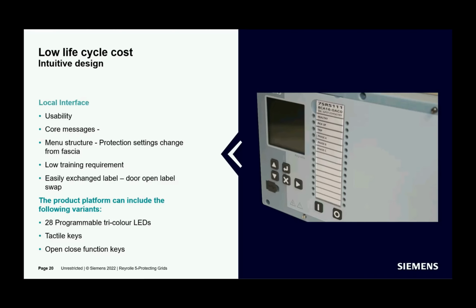What is more, the user can change all the settings of the protection configurations inside the fascia. For example, after entering the predefined settings password, the menu allows you to change any threshold value of any protection configuration, or enable or disable the protection functions altogether. So you don't need the configuration software once the relay is initiated and started. The menu is simple and button interaction with the menu is intuitive. Therefore, this provides low training requirements for the users.